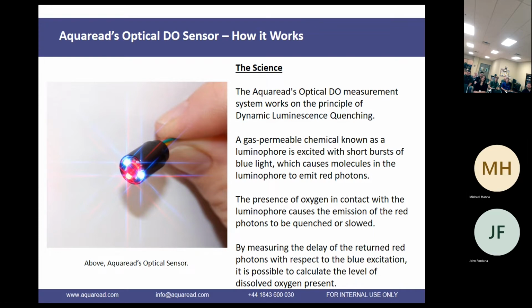The calibration is stored for up to 6 months. So you can actually not calibrate it for quite some time, and it will stay stable. We have scientific research, or lab tests, that show it stays stable for that length of time. With a galvanic sensor, which obviously is not optical, they tend to drop off. You have to regularly change the electrolyte solution. You have to change the membrane cap because they degrade. The reason you have to change those is that it's a chemical reaction. The reason optical DO sensors have become so popular is that they just use light. So the only thing you really need to worry about is the membrane cap.